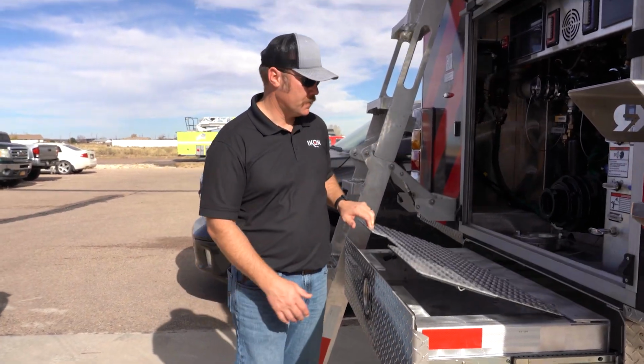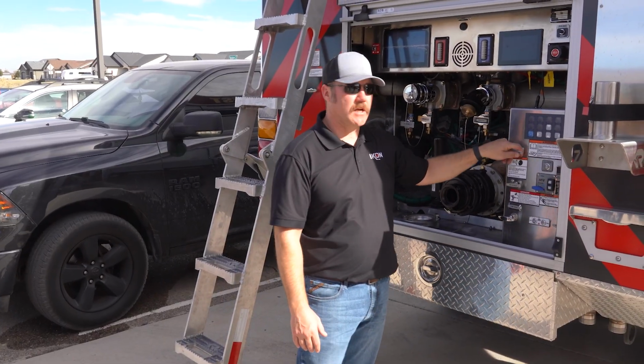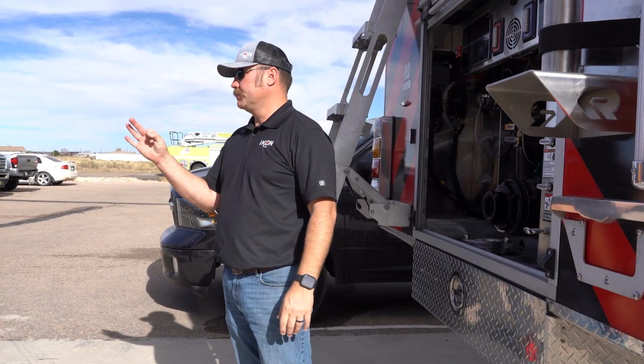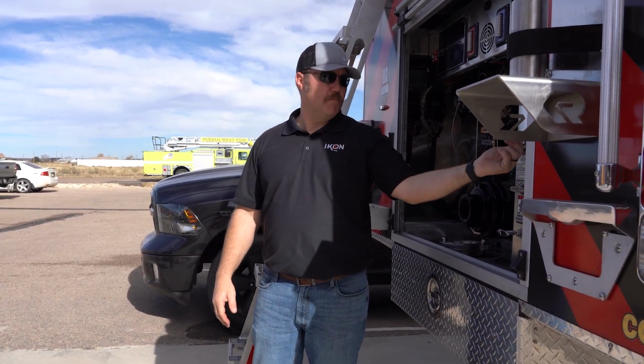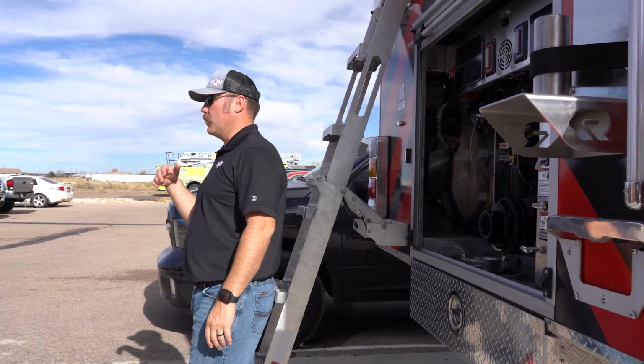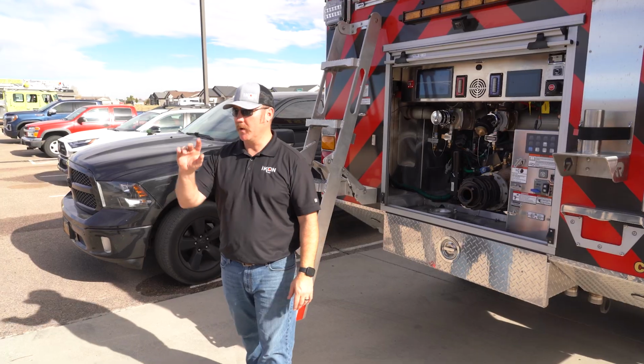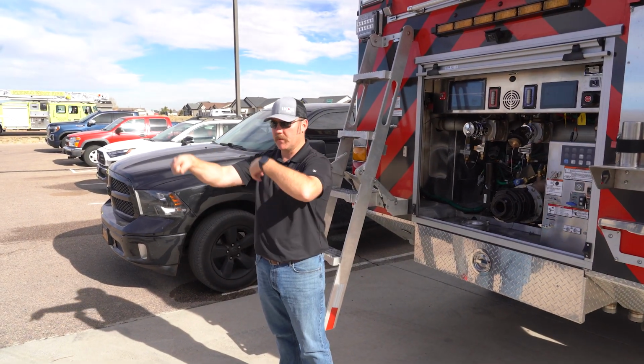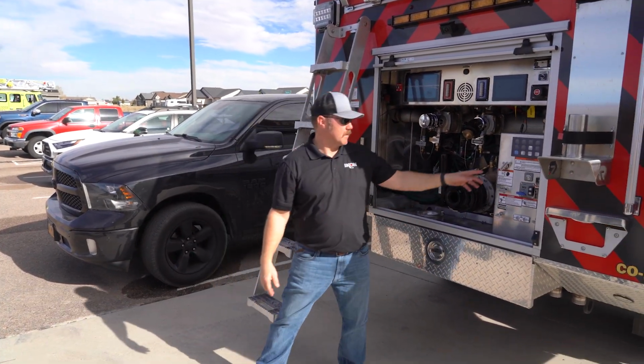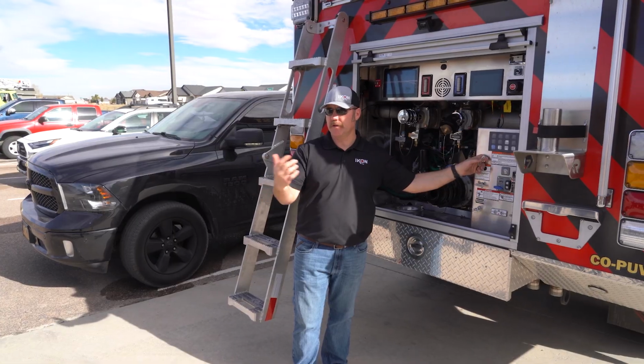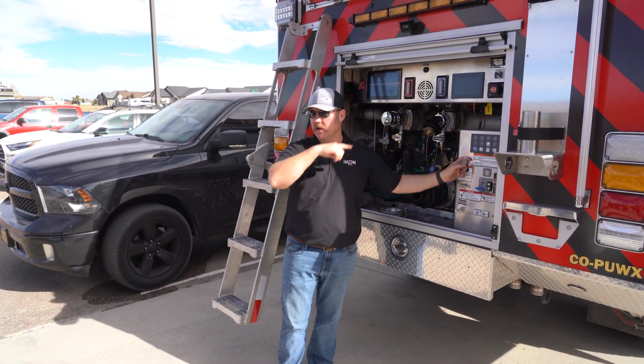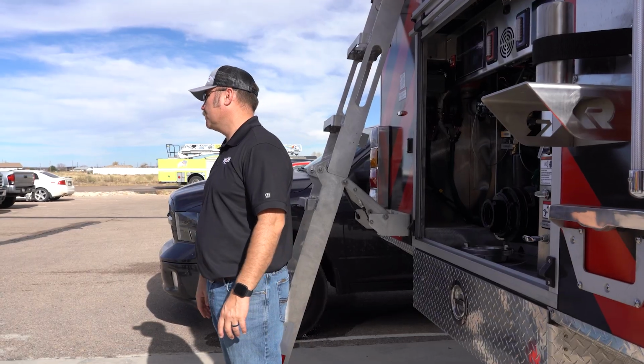Heat exchanger - pretty much the heat exchanger is a quarter-inch water line. When I open this up, it's similar to a pump recirc, right? If I open up my tank fill, I'm recircing my pump. This is doing the same, except instead of opening up the tank recirc, it's just taking a little bit of the pump water and putting it around the pump to try to keep it from heating up.